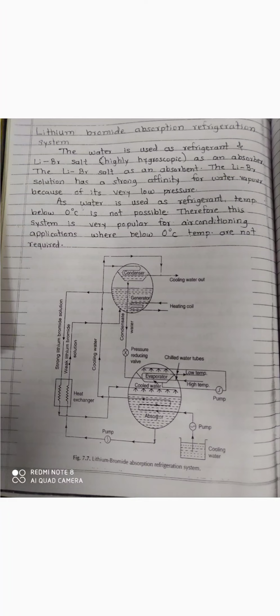This weak solution from the absorber is pumped to the generator through a heat exchanger. In the generator, with the help of a heating coil or heating media, a separation takes place between lithium bromide and water. As the boiling point of water is low, water gets vaporized, and whatever solution remains is a strong lithium bromide solution, which returns to the absorber through the heat exchanger.